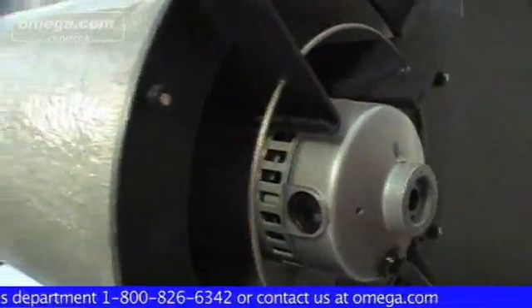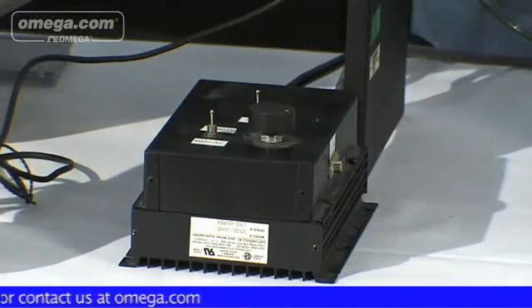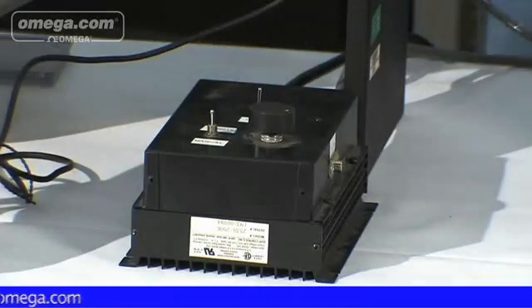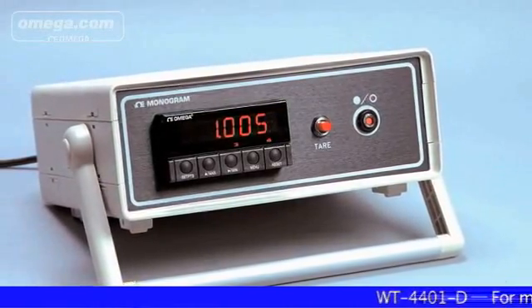A powerful 12-amp motor delivers airflow from 0 to 10,000 RPM. Airflow is adjustable to give a particular flow rate with the very precise motor control unit. The uniform flow rate is determined by monitoring a highly repeatable differential pressure sensor, which has been calibrated to each individual wind tunnel as a system.